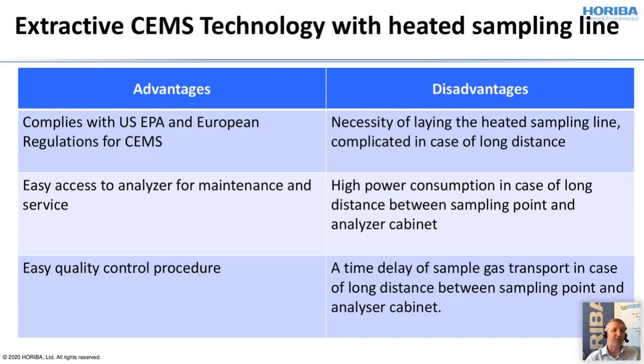Some comparison, the extractive CEMS technology with the heated sample line. We have some advantages. First of all, it complies with US EPA and European regulation for CEMS. Then it's also easy to access the analyzer for maintenance and service because it's located at the base floor, somewhere at the ground. You can easily go there. And the quality control procedure is also done quite easily. Of course, no advantage without disadvantage. Talking already about this heated sample line, it needs to be laid. And if you think about laying a heated sample line for 50 or even more meters, then it's quite complicated in case of such long distances. What I mentioned already is the high power consumption in case of long distances between the sampling point and the analyzer cabinet.